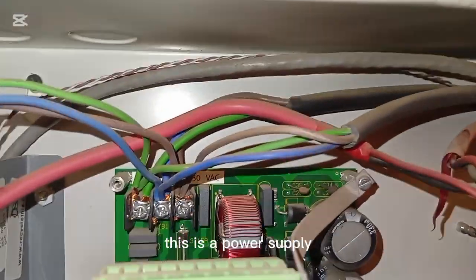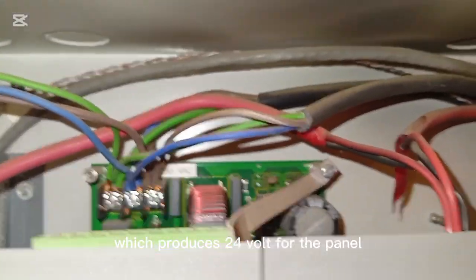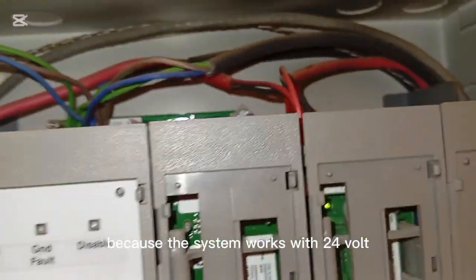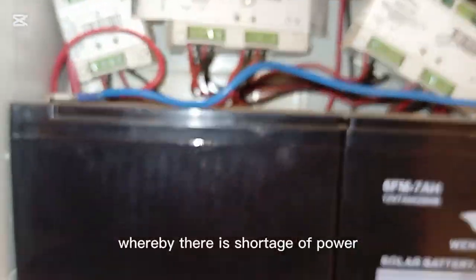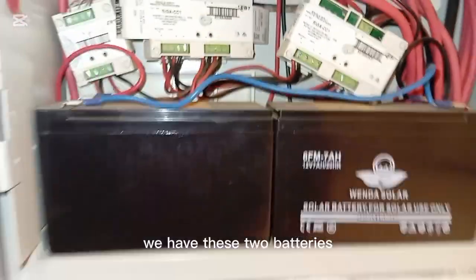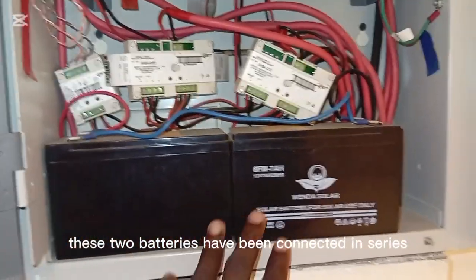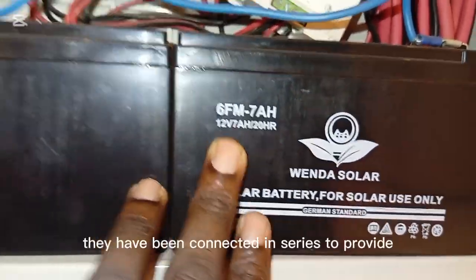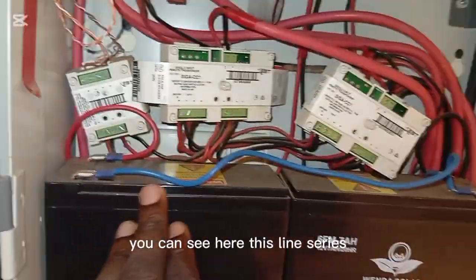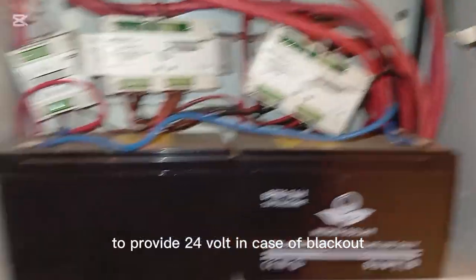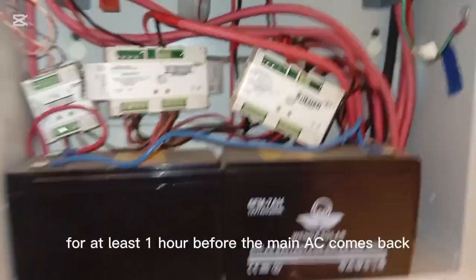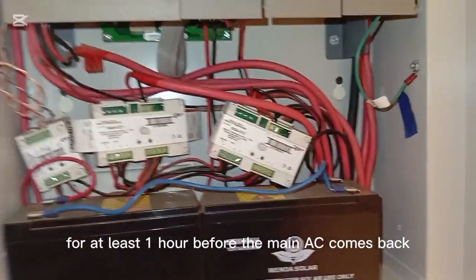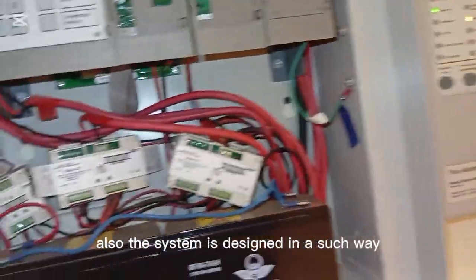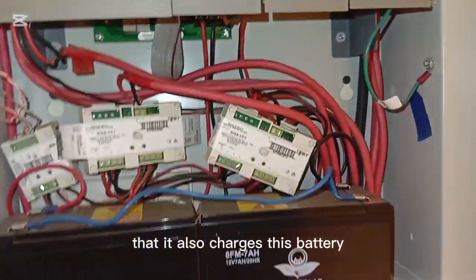You can see this is a power supply which produces 24 volt for the panel, because the system works with 24 volt. Then in case of a blackout, whereby there is a shortage of power, we have these 2 batteries. These 2 batteries have been connected in series. They are 12 volt batteries. They have been connected in series, you can see here this line, to provide 24 volt in case of blackout for at least 1 hour before the main AC comes back. Also, the system is designed in such a way that it also charges this battery.